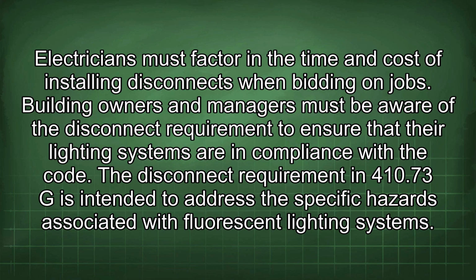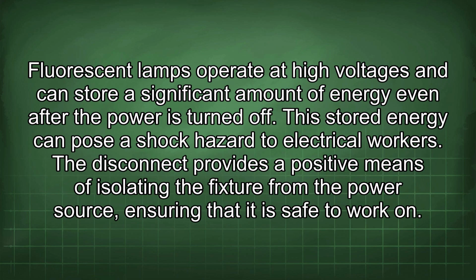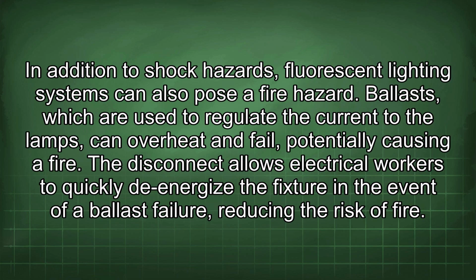The disconnect requirement in 410.73G is intended to address the specific hazards associated with fluorescent lighting systems. Fluorescent lamps operate at high voltages and can store a significant amount of energy even after the power is turned off. This stored energy can pose a shock hazard to electrical workers. The disconnect provides a positive means of isolating the fixture from the power source, ensuring that it is safe to work on. In addition to shock hazards, fluorescent lighting systems can also pose a fire hazard. Ballasts, which are used to regulate the current to the lamps, can overheat and fail, potentially causing a fire. The disconnect allows electrical workers to quickly de-energize the fixture in the event of a ballast failure, reducing the risk of fire.